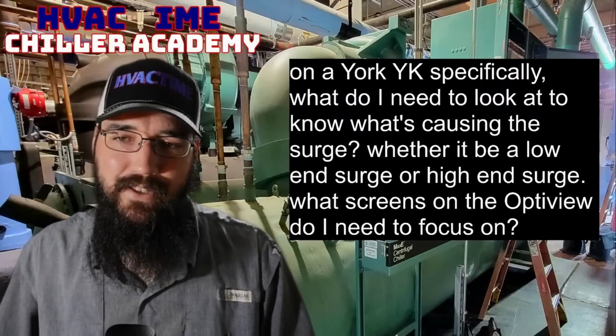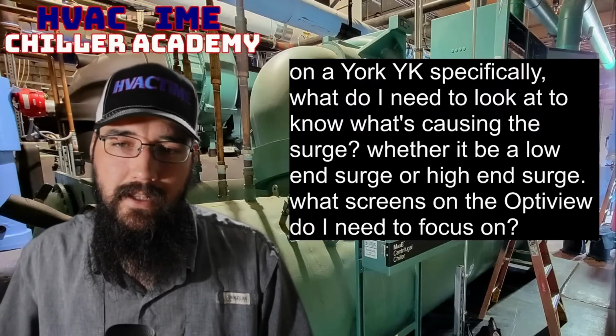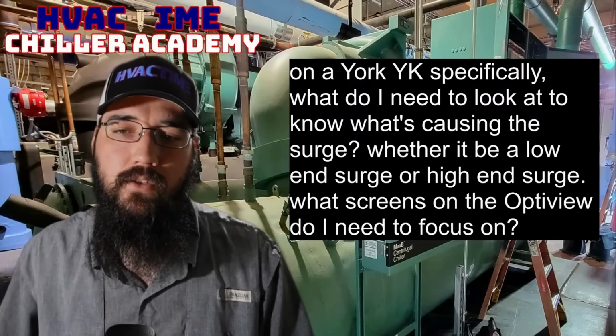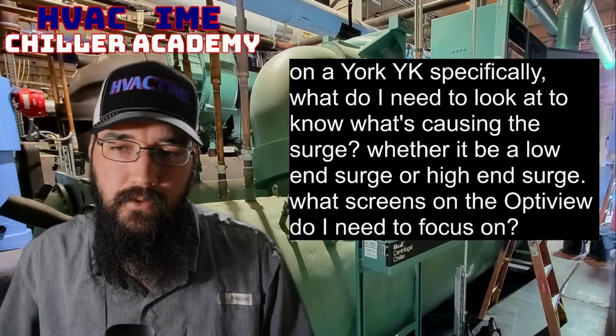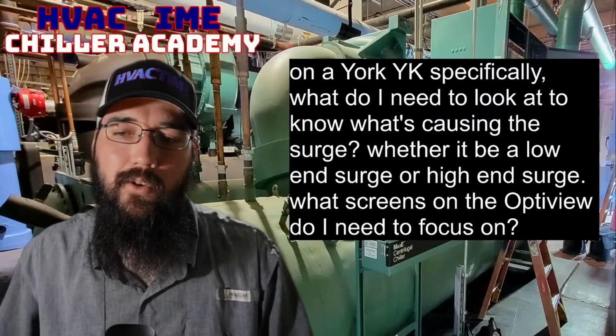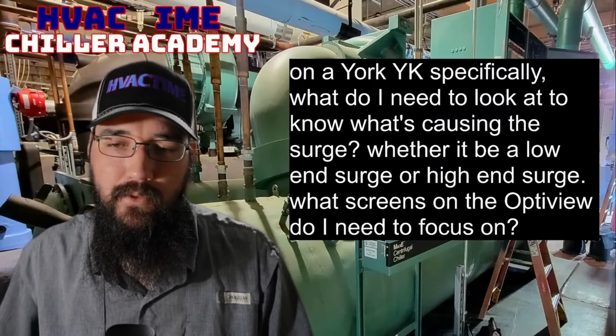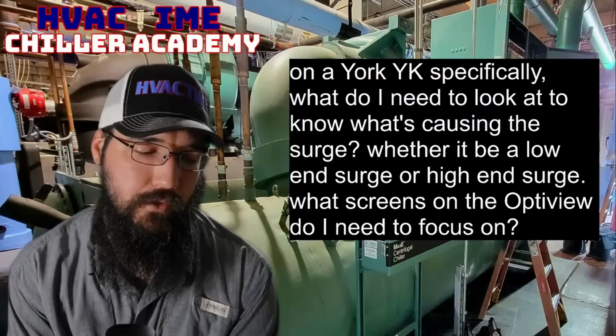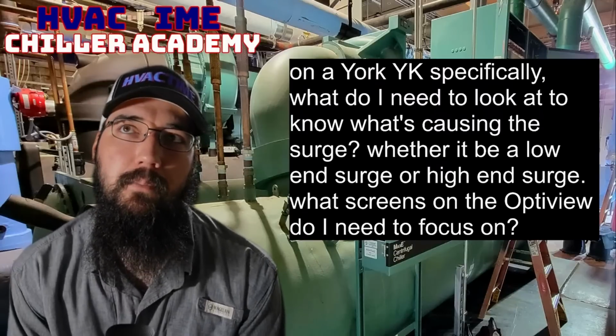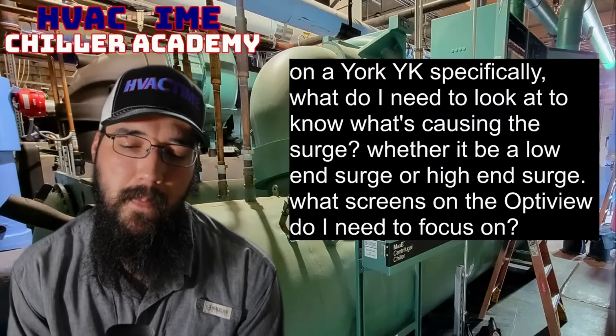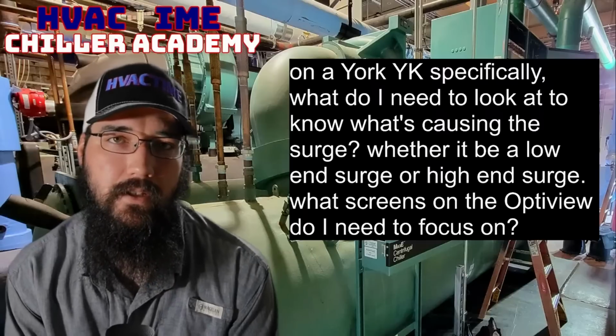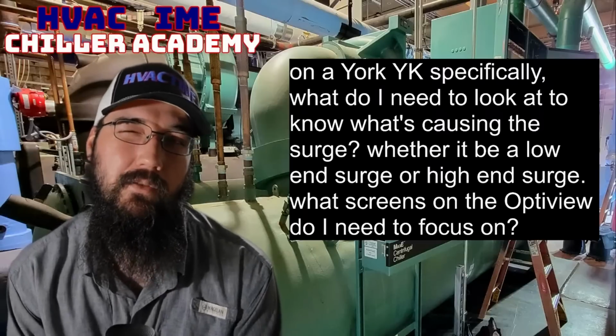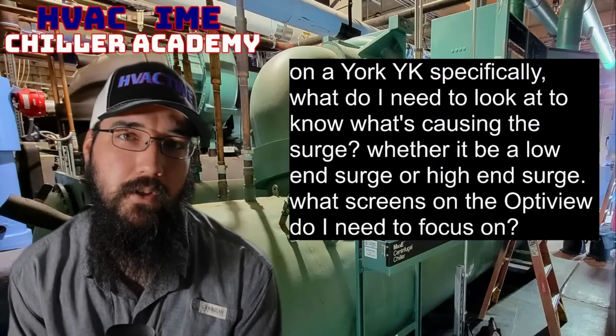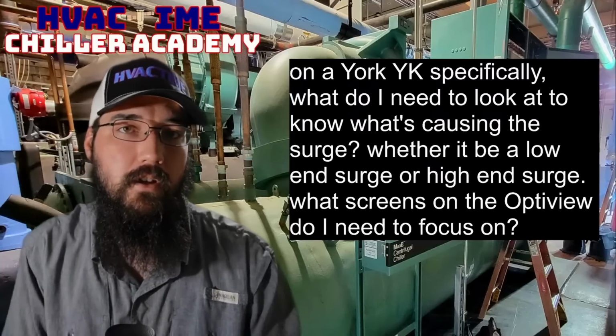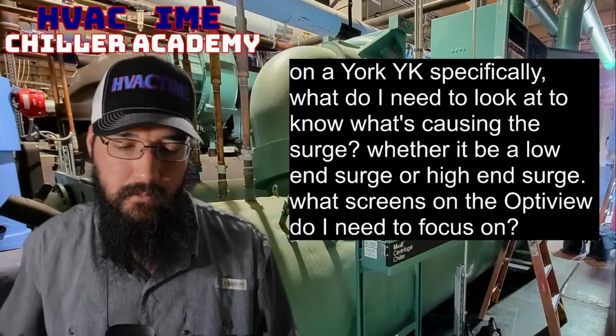On a York YK specifically, what do I need to look at to know what's causing the surge, whether it be a low-end surge or high-end surge? On what screens on the OptiView do I need to focus on? There's the screens that are going to do the most for you. If you have a VGD, the VGD screen, which is inside of the compressor screen, so it's a sub-menu under the compressor. Granted, you have to be logged into service mode to see some of these.